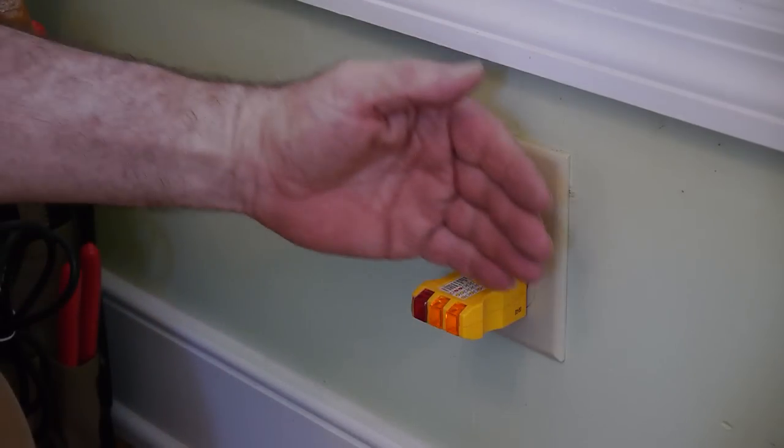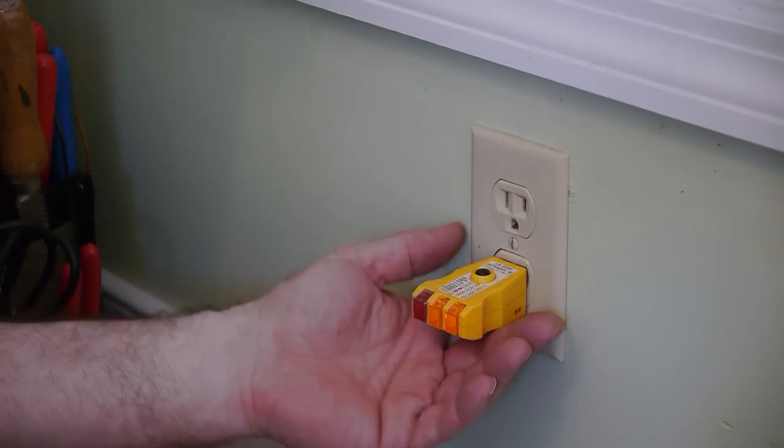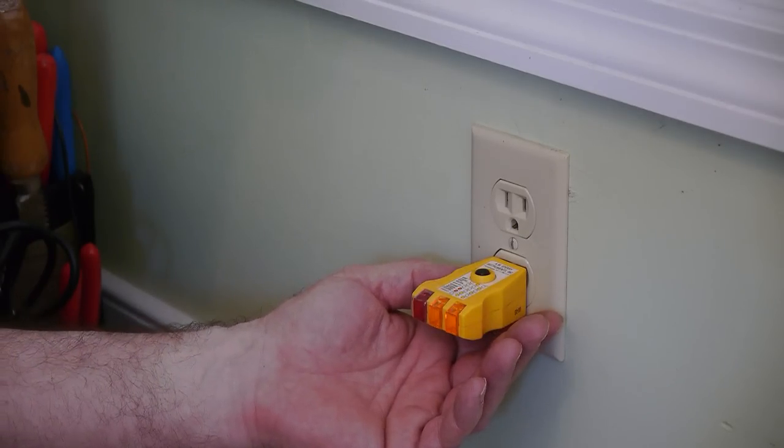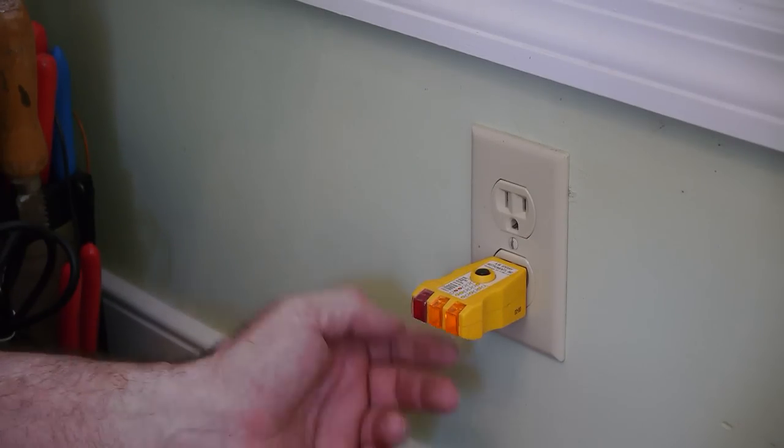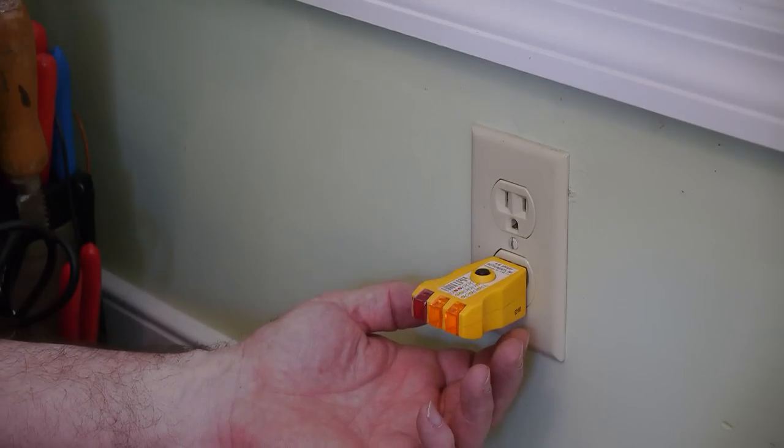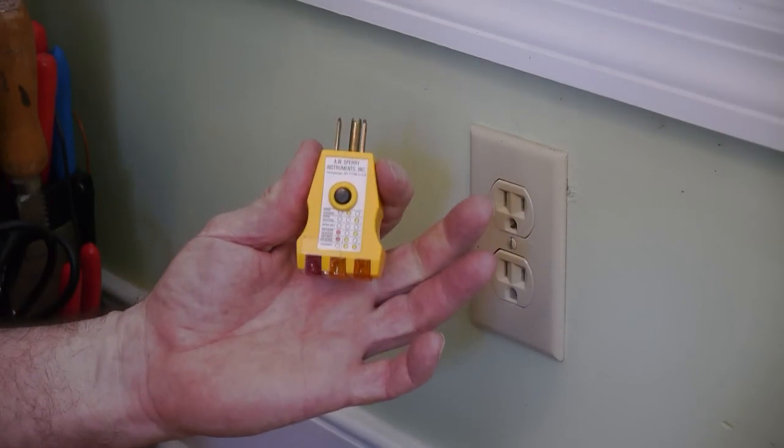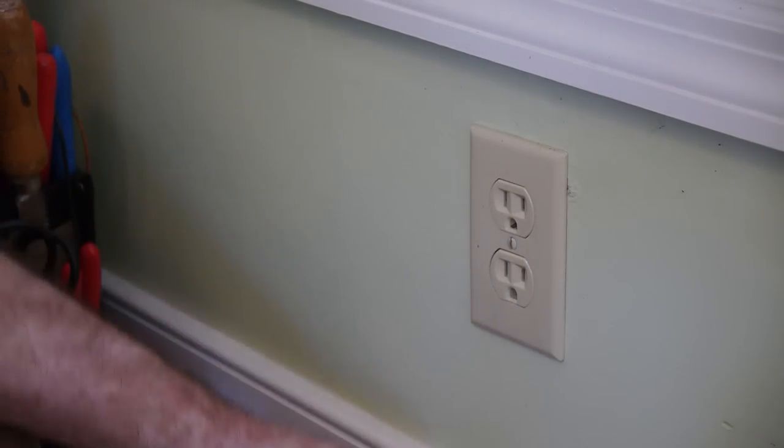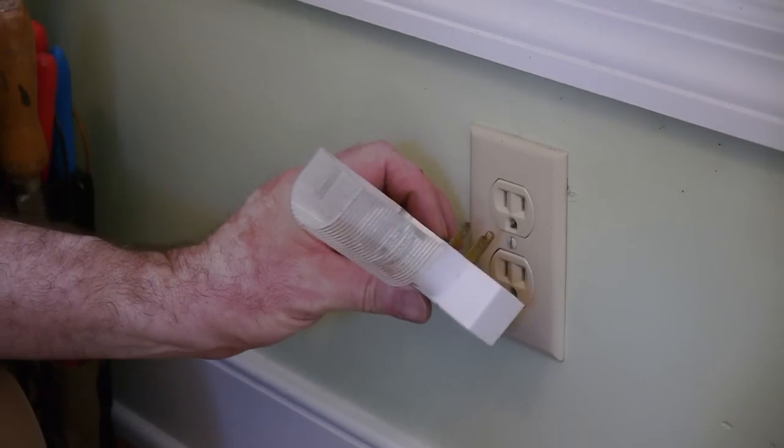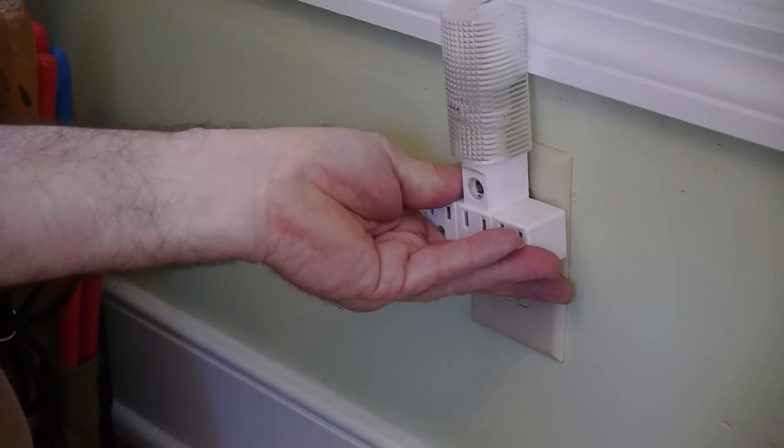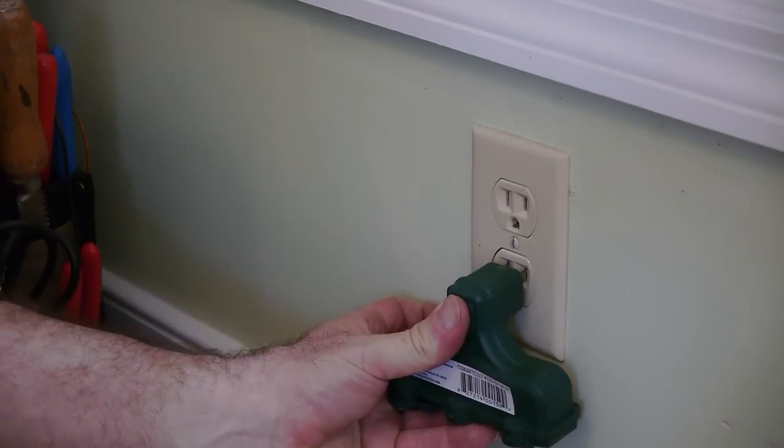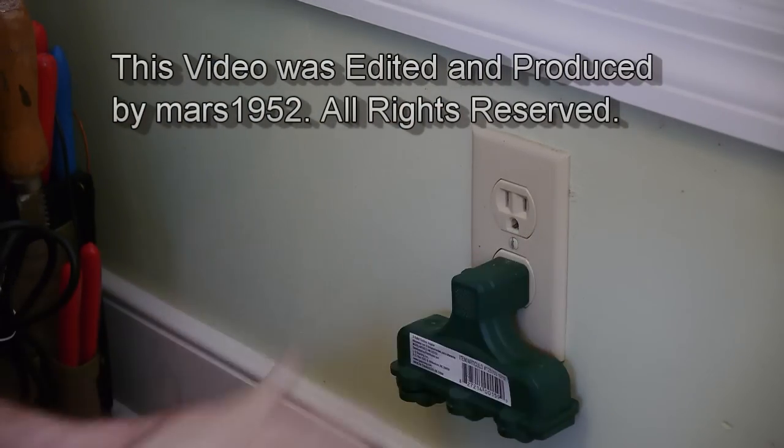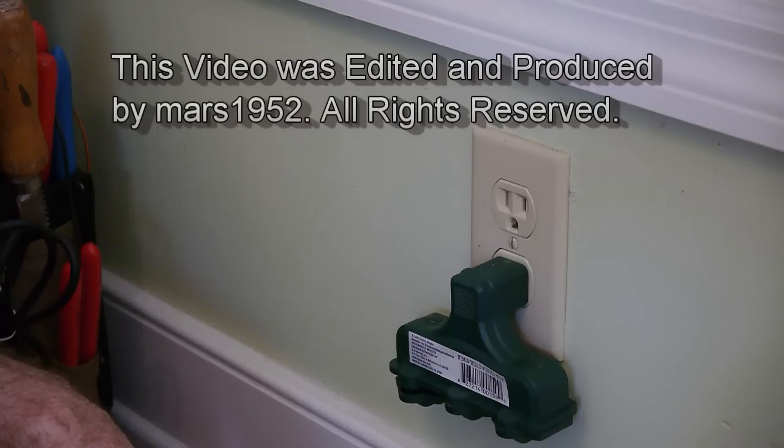Well, I'm back and hopefully you can see that all three lights are actually the two ambers are illuminated and the red is not. That indicates that both of the polarity is correct and the ground is correct. If the ground is incorrect, it would illuminate red. And there's indicators on here to show you what's what. But two ambers is good. So it's done, ready to go. So now I can plug these in like they're supposed to be. Have fun. Try not to kill yourself.